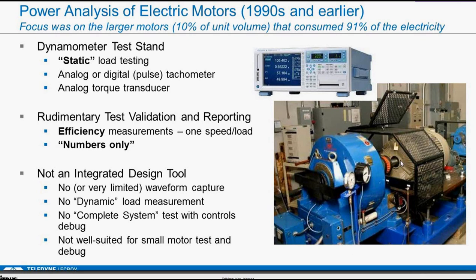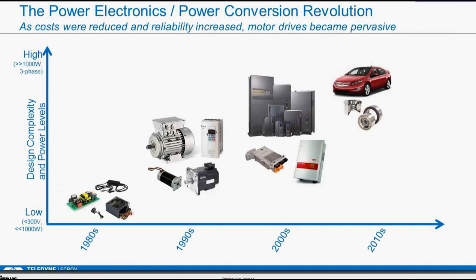It's what I would call the static load test. There'd be a dynamometer to put a load on it. You'd use something like this power analyzer. You calculate efficiency at one speed and load, and you get a number that was X percent efficiency. Historically, this was really a final validation tool. It's not an integrated design tool. It doesn't really help you with dynamic load measurements. Also, it doesn't let you debug your control, your power conversion section at the same time to see if that's affecting your efficiency. But big things are changing.